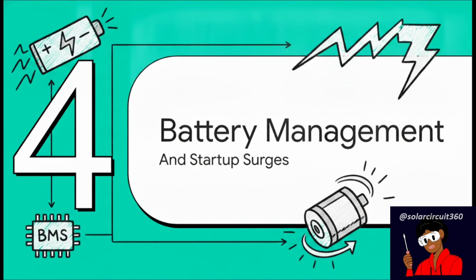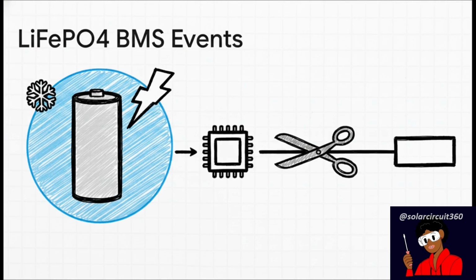Section 4. The battery management system and startup surges. Now let's look at two specific, kind of stealthy accomplices in our mystery. If you're running modern lithium iron phosphate or LiFePO4 batteries, the battery management system, or BMS, adds a whole new layer to the puzzle. Your BMS might just completely disconnect the battery pack to protect against overcurrent, a single low voltage cell, low temperatures, or even cell imbalance. When that happens, the inverter instantly loses its DC supply and completely shuts down. Naturally, you might blame the inverter, but in reality, the BMS is just doing its job perfectly, stepping in to cut the power and protect the battery chemistry.